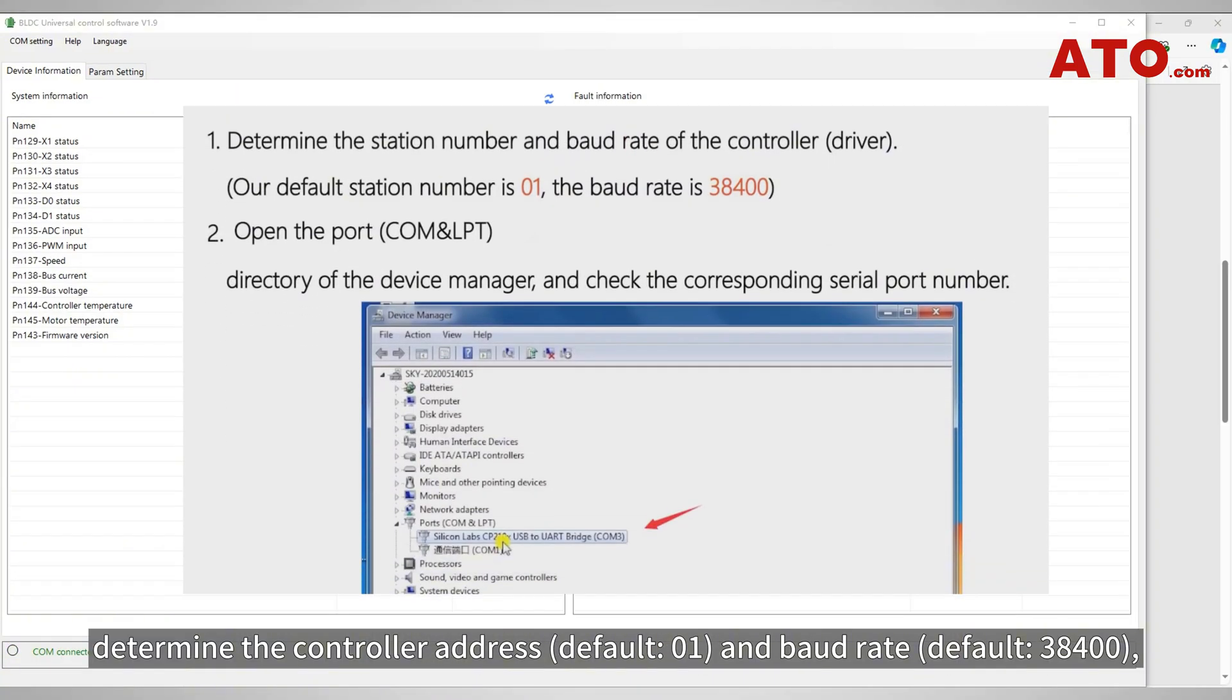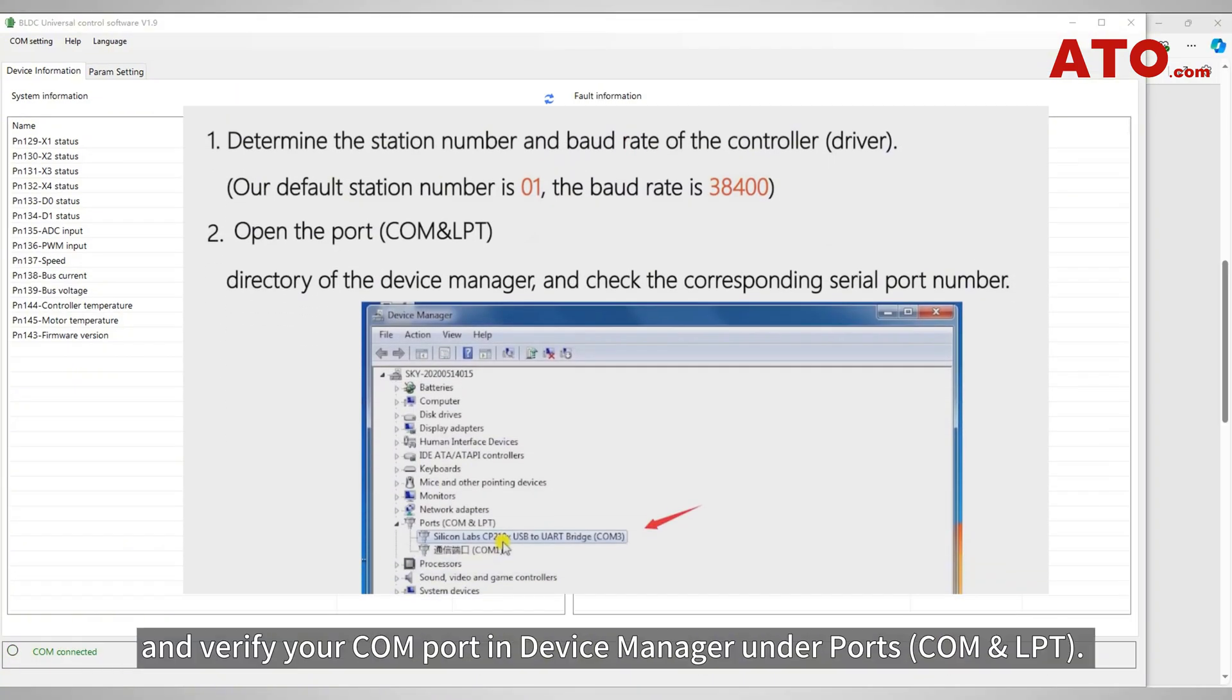If connection fails, determine the controller address and baud rate, and verify your COM port in Device Manager under Ports, COM and LPT.